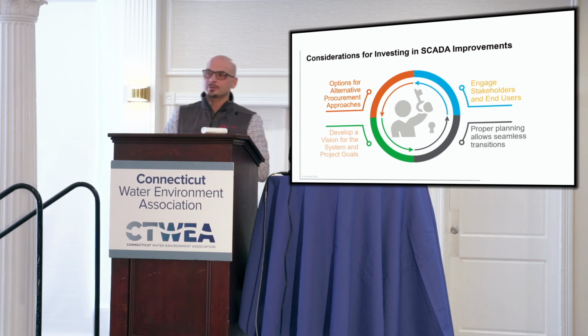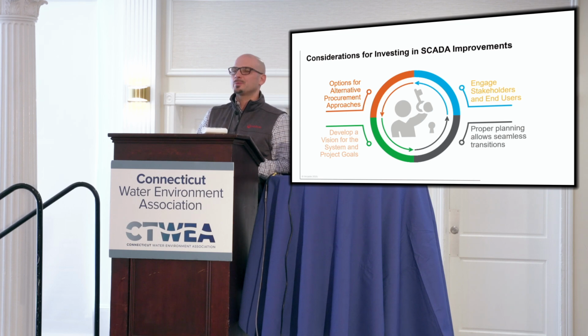Yes, we monitor all that. We had an instrumentation upgrade about two years ago that was finalized last year. We measure DO, and we have SCADA set points so that if something changes in the process, the DO adjusts and the blowers turn up accordingly. We also have ORP probes, ammonia, and nitrate sensors, so we can see in real time what's going on. There's regular maintenance, cleaning, and calibration needed, but our team is efficient in keeping those parameters easy to monitor.